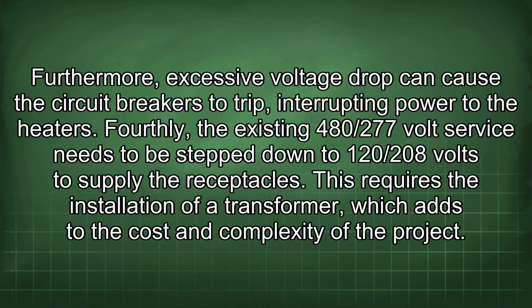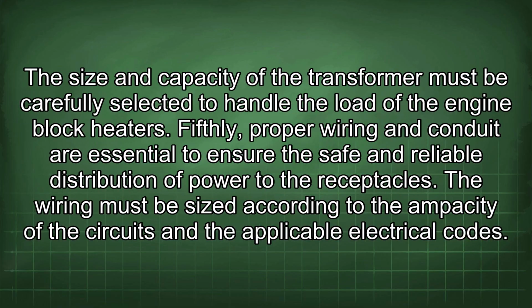Fourthly, the existing 480/277 volt service needs to be stepped down to 120/208 volts to supply the receptacles. This requires the installation of a transformer, which adds to the cost and complexity of the project. The size and capacity of the transformer must be carefully selected to handle the load of the engine block heaters.